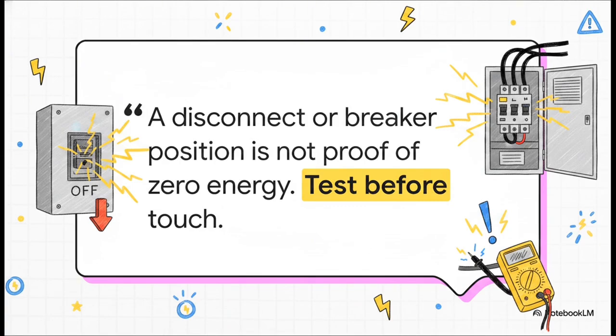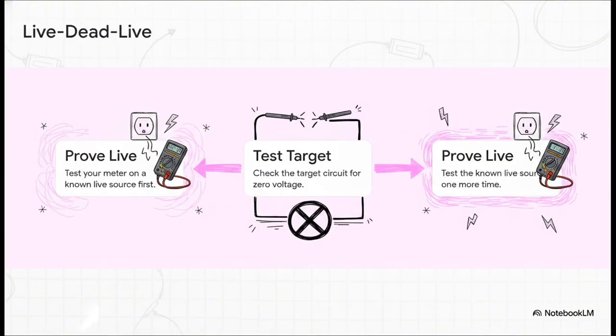Plus, if you open a main service panel, the parts ahead of that main disconnect are still fed directly by the utility and remain live. That's why the golden rule is always test before touch. Assume every wire is fully energized until your own meter proves otherwise. To confidently verify zero energy, pros use what's called the live-dead-live method. It's a three-step dance.